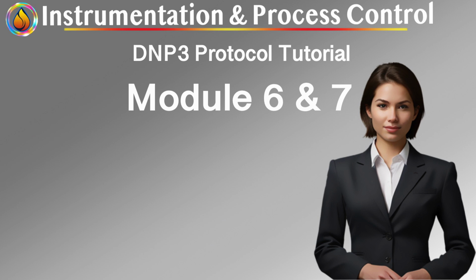Unsolicited reporting mode. In unsolicited mode, outstations transmit responses without prior requests, typically used for event data, and requires prior enabling and authorization. Unsolicited messages are still structured as valid DNP3 responses and are subject to confirmation and retry mechanisms.